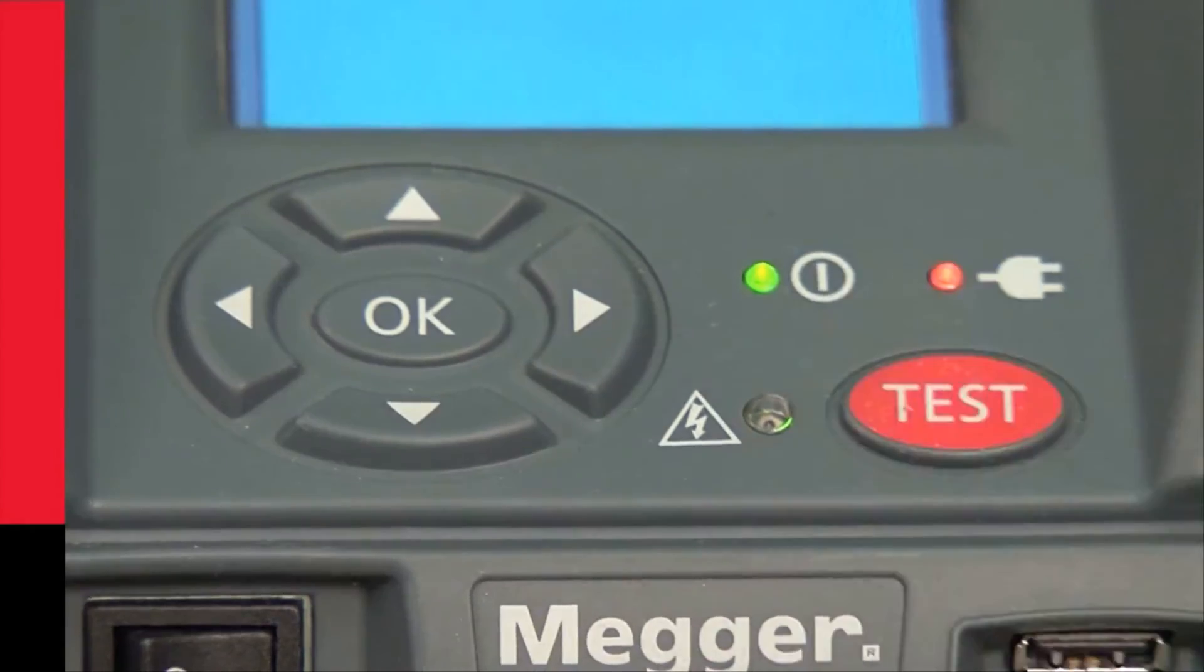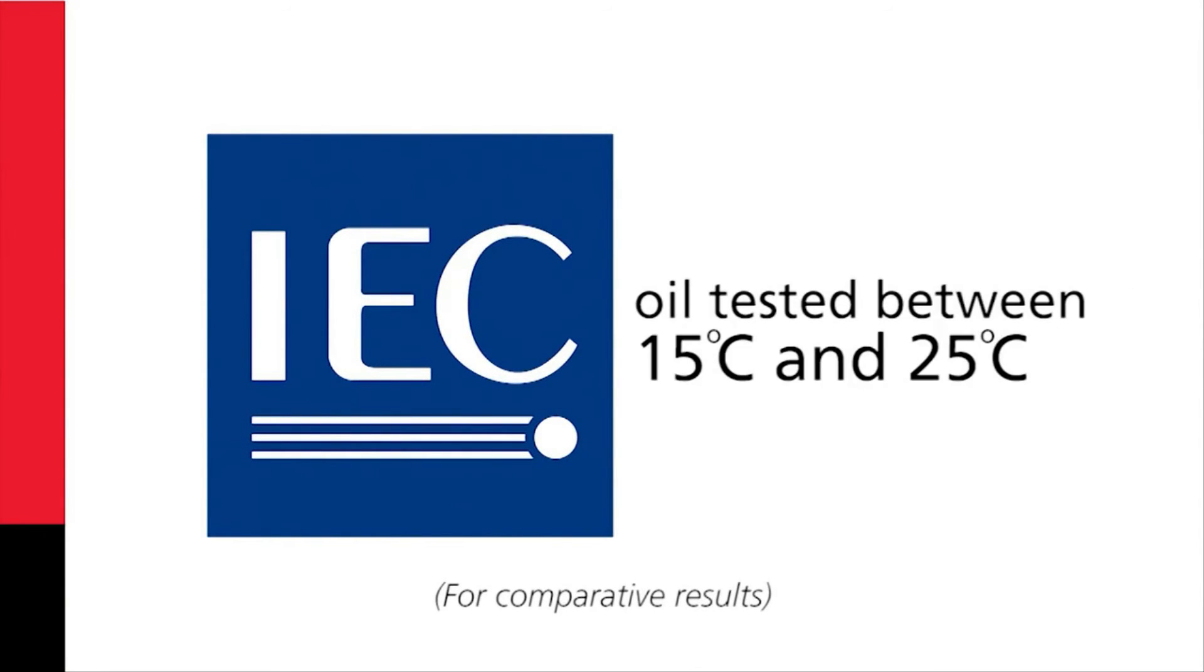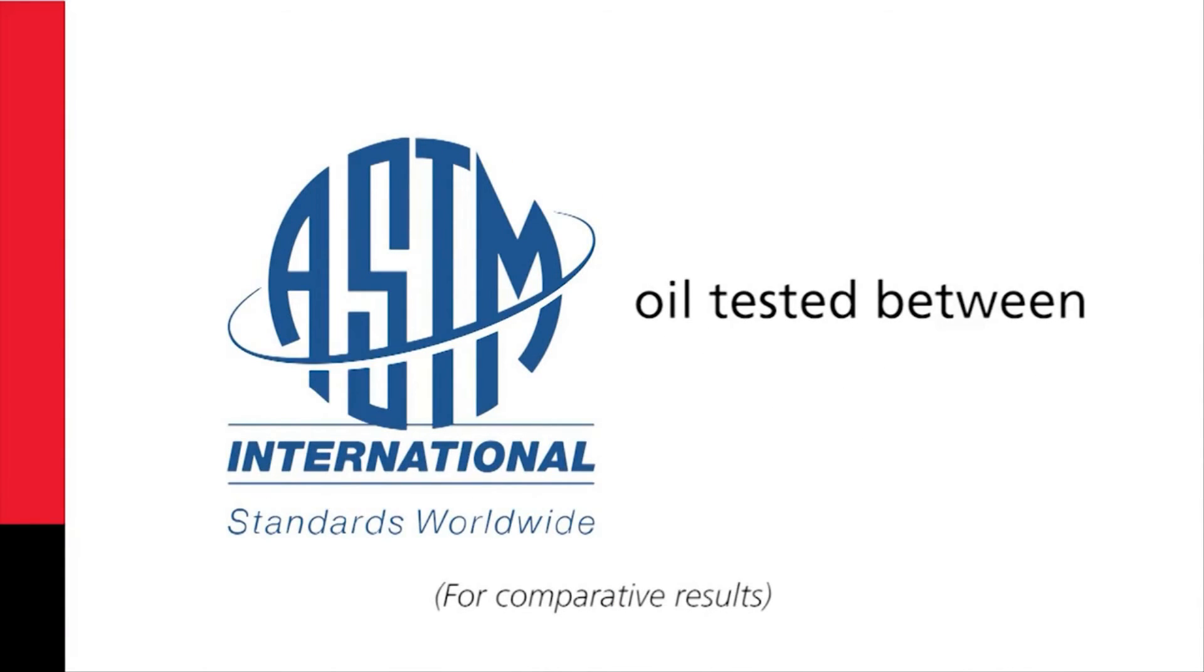Remember, a sample should only be tested once. IEC requires that the oil sample be tested at a temperature between 15 and 25 degrees centigrade, and ASTM 20 and 30 degrees centigrade.